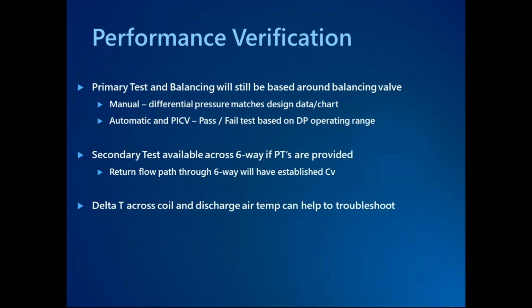Secondary tests are always available as well with pressure drop through your 6-way. I mentioned earlier that the 6-ways all have a CV disc designed to be inserted or designed into the body that goes in the outlet bottom port of both the heating and cooling. So if you're able to measure the differential pressure on the return line coming back from your dual temp zone to your return heating or cooling, and with the knowledge of where that CV is, you're able to double check flows in this sense as well. And then lastly, delta T across the coil or discharge temp are always a viable way of troubleshooting the system.